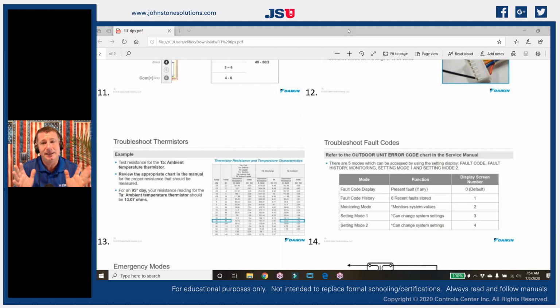So we have to change our mentality. If we were talking about standard HVAC low voltage wiring on unitary systems, on legacy wiring, it's all 24 volt AC. We run that through all of our sensors. Well, when we get into inverters, we're just going to use that 5 volt DC to run through everything, all of our temperature sensors and pressure transducers. So our temperature sensors are just going to change resistance based on their temperature.